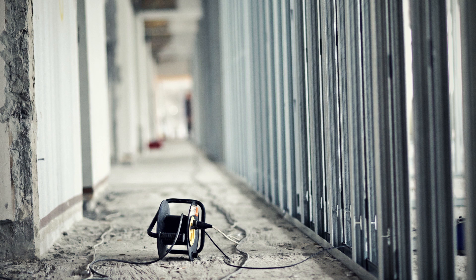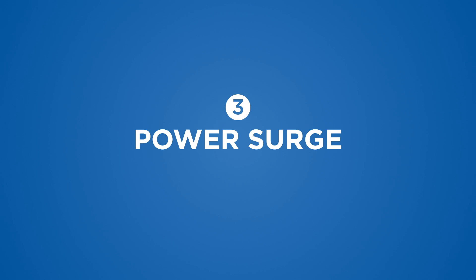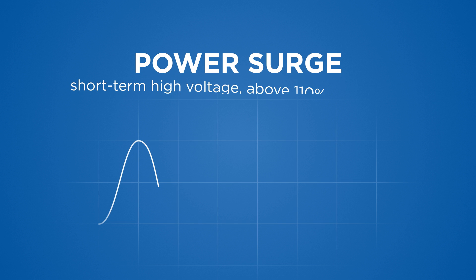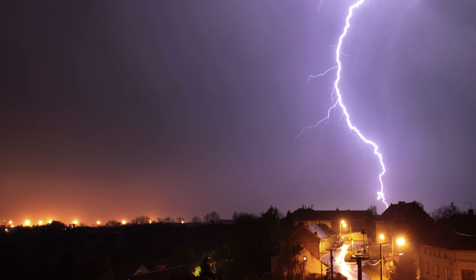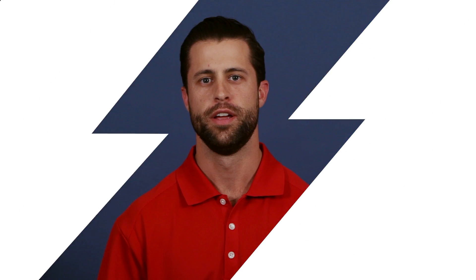In addition to crashes, sags can damage hardware. Power surge or power spike is short-term high voltage above 110% of nominal. This can be caused by a lightning strike and can send line voltages to levels in excess of 6,000 volts. A spike almost always results in data loss or hardware damage.